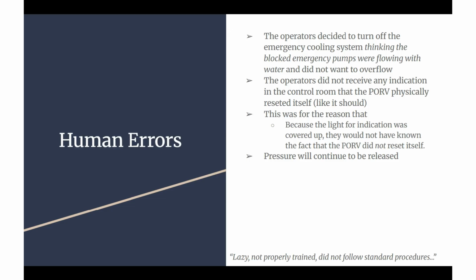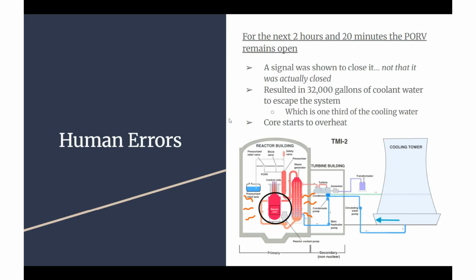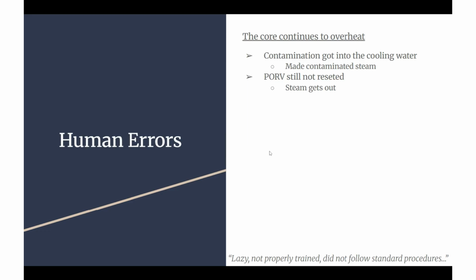The operators did not receive any indication in the control room that the PORV physically reset itself like it should. This was because the light for indication was covered up, so they would not have known that the PORV did not reset itself. Pressure will continue to be released. For the next 2 hours and 20 minutes, the PORV remains open. A signal was shown to close it, not that it was actually closed. It resulted in 32,000 gallons of coolant water escaping the system, which is 1/3 of the cooling water. So then the core starts to overheat. As the core continues to overheat, contamination got into the cooling water. It made contaminated steam. The PORV is still not reset, so then steam gets out.